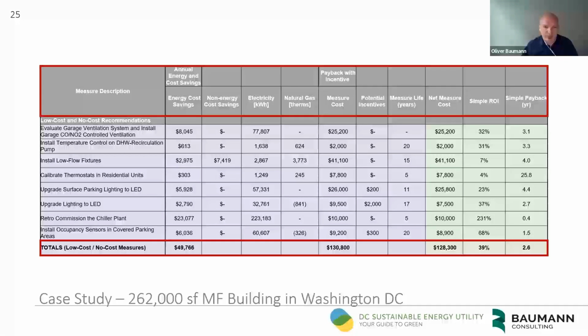All these measures were recommended. Even the one measure of calibrating the thermostat in the residential units, which has basically no reasonable payback at 25.8 years, still makes sense because it improves thermal comfort tremendously. If a thermostat is off by 2, 3, or 4 degrees, as we saw through measurements, it won't control to the right temperature, and the person living in that apartment will constantly adjust it, overheating or overcooling depending on the offset, leading to space heaters or coolers in those spaces. So that's definitely a measure that makes sense, even though the simple payback time doesn't indicate it's of value.